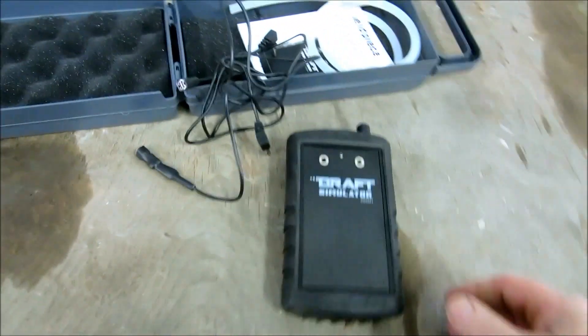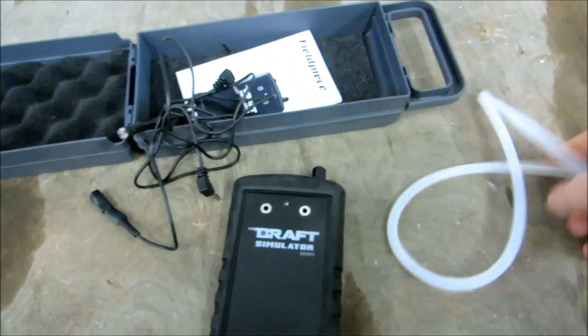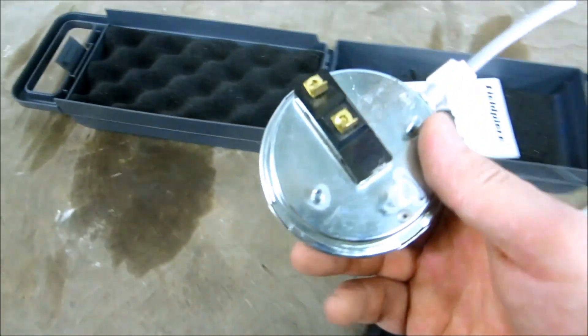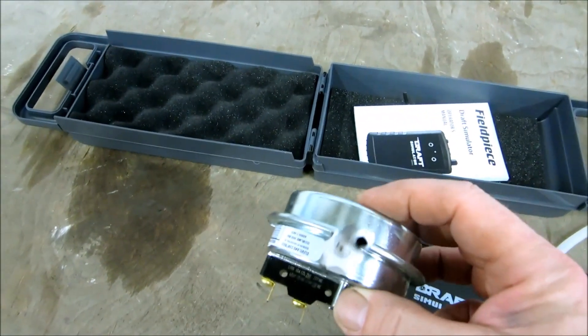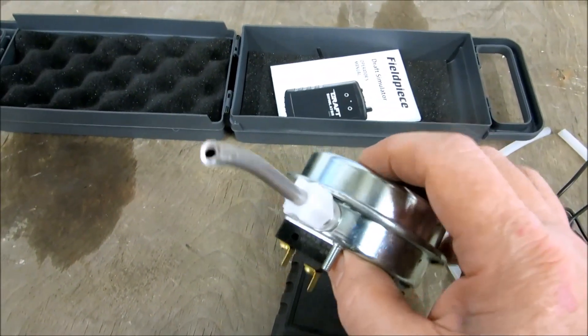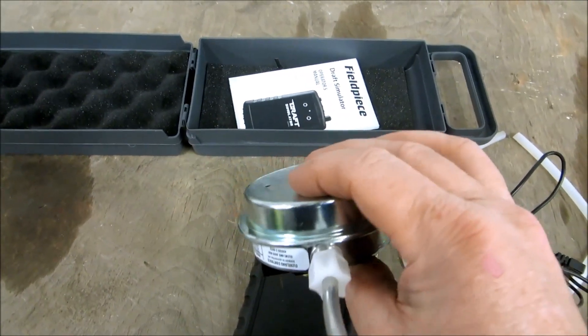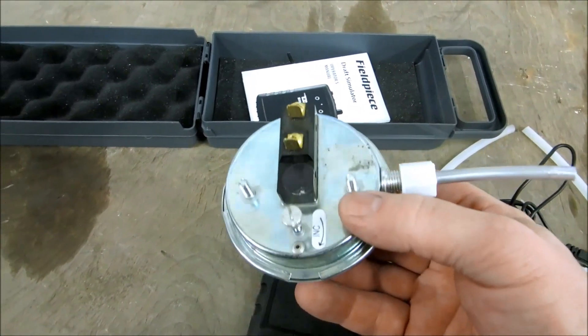I got one over there I'm going to check. It comes with a couple of tubes, and you can pull a vacuum on a switch to check if it's any good. They say you want to make sure you take it out of the furnace, make sure it's not full of water. I know this one's good. This one was in my truck. This is for a power venter. It's the only one I have, but let's see how this thing works.